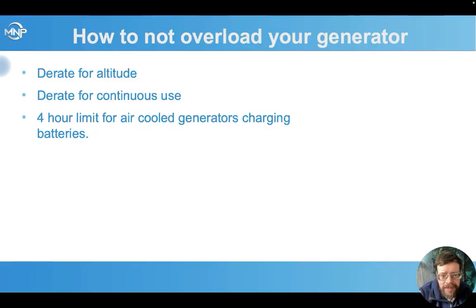And one thing we can do to mitigate that is really derate them, and we might only be pulling, say, 10 kilowatts out of a 20 kilowatt standby generator when we take all these derates into account to really keep it happy long term. If you're just using it a few hours a year for backup power, it's not as critical. But if it's a situation where, in deep dark wintertime, you're running it every afternoon for 2 or 3 hours, that's really where you want to think about, how can I make this generator last longer?